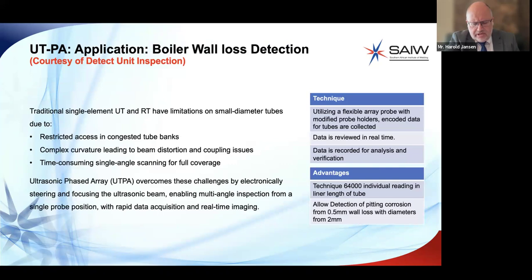Traditional single element UT and RT have limitations on small diameter tubes due to restricted access in congested tube banks, complex curvature leading to beam distortion and coupling issues, as well as time-consuming single angle scanning for full coverage. Ultrasonic phased array overcomes these challenges by electronically steering and focusing the ultrasonic beam, enabling multi-angle inspection from a single probe position with rapid data acquisition and real-time imaging.